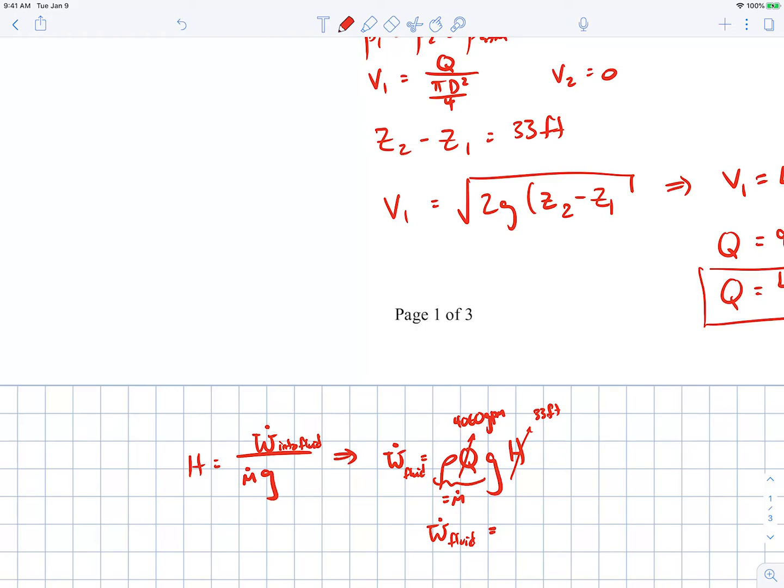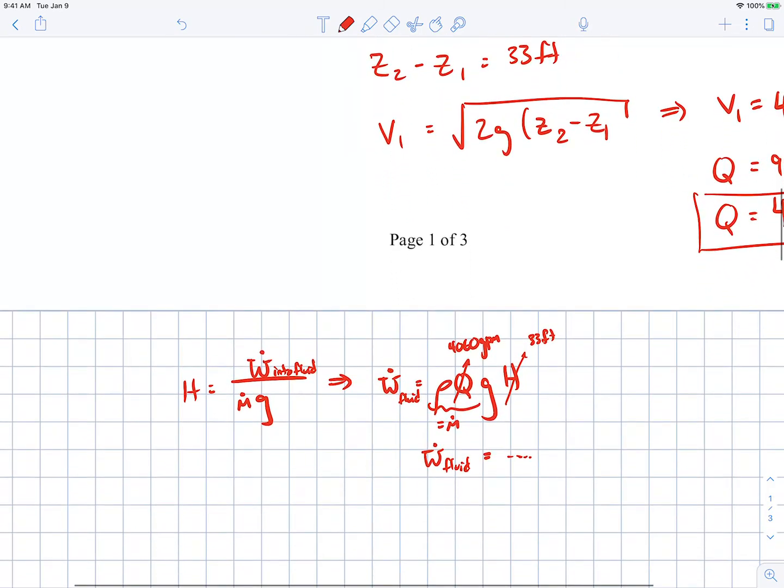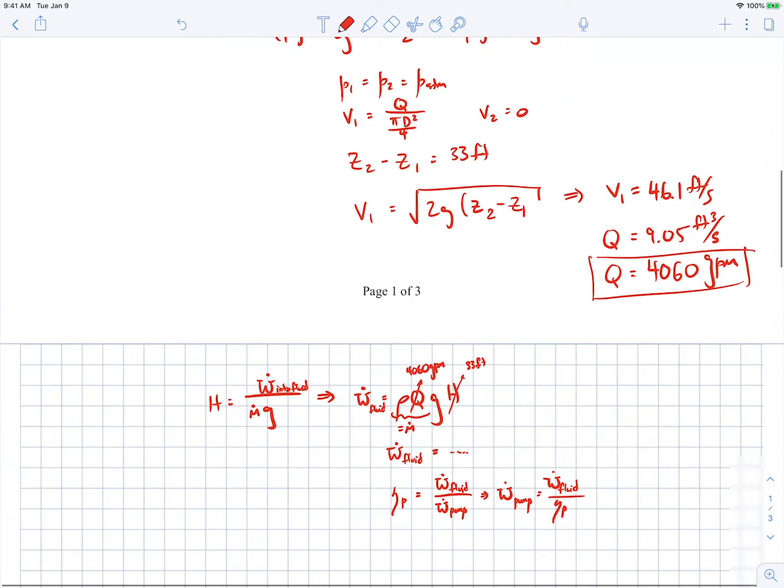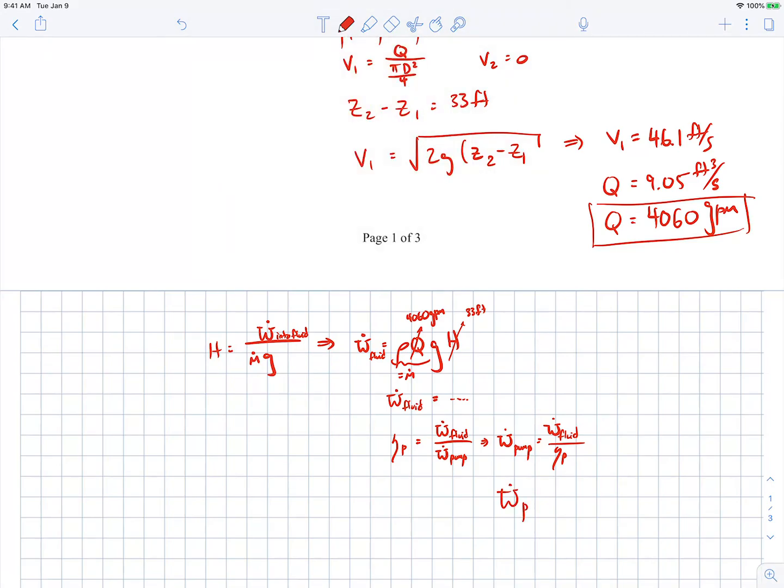So we can then calculate what the power into the fluid is. That's the power into the fluid. If you want the power into the pump, you have to make sure you use the efficiency. So the efficiency of the pump is going to be the power into the fluid divided by the power into the pump. So you can find the power into the pump is the power into the fluid divided by the pump efficiency.